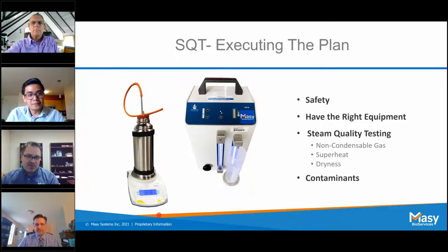There's also a large device there that's shown, which is our condenser. So that is used for the non-condensable gases testing. Internally, what that device does is it condenses the steam. So it is hooked up to that test pipe that we showed earlier. And internally, it condenses that steam and is able to separate the water from any non-condensable gases that are present.